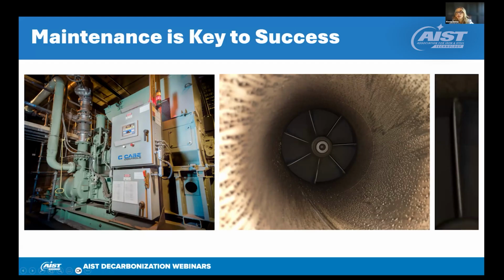So this machine that would typically last 30 to 40 years, after 2 years, all the internal air passages were coated with dirt and debris. The impeller was coated with dirt and debris. You can see this in the enlargement here of the impeller blade. It's rounded out, so it's begun to lose efficiency.